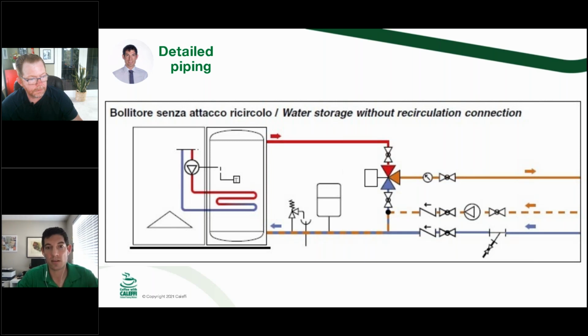And something that should be mentioned is that these point of distribution mixing valves, like the Legio mix and the MixCal Plus, the MixCal that are going to be in the mechanical room, are not scald protection devices. So these are meant to mix the temperature down to send out to the building. They are not the last line of defense. You want to use a point of use mixing valve to have the ultimate stop, basically, to make sure that the hot water doesn't hit a tap, and that's going to prevent the recirc creep issue as well. That's an important piece of it. So nursing homes and things like that, for sure. The Legio mix, as well as it will work to close off that hot water, isn't the ultimate. That's what point of use mixing valves right under the sink or right by the tub are built for.